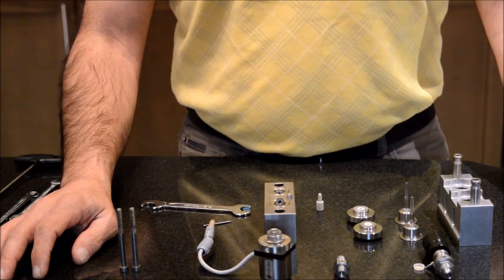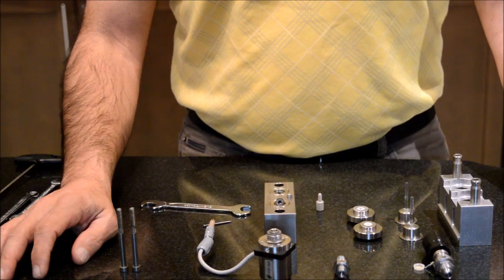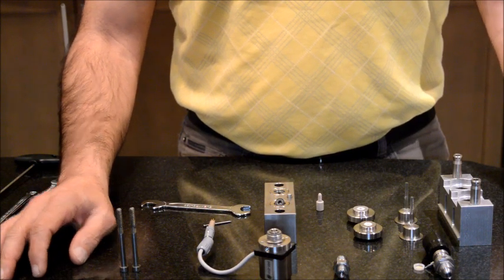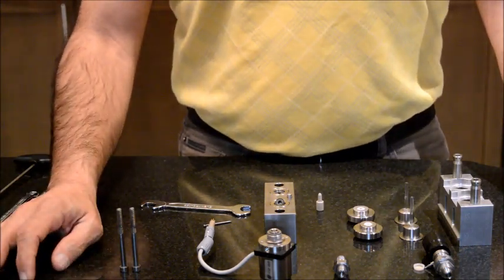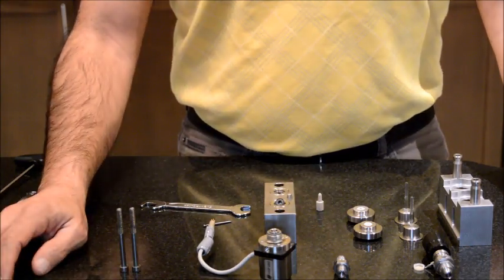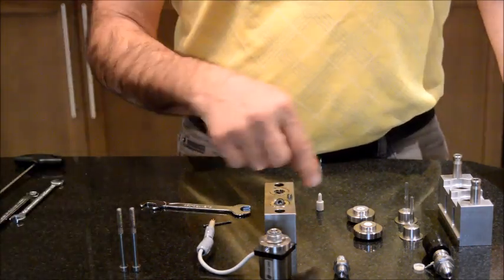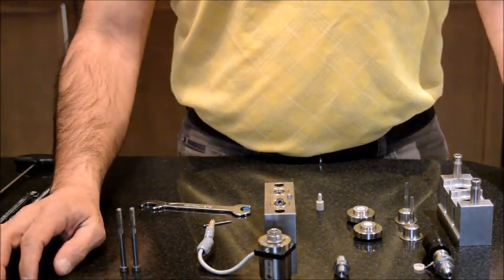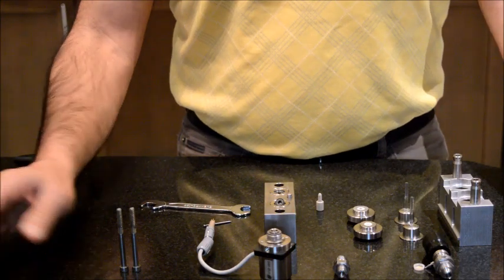When you have these crystals forming inside the pump it's going to damage your check valves, you're going to damage your pump seals and you're going to see the system shutting down with no flow, major leaks and so on and so forth.